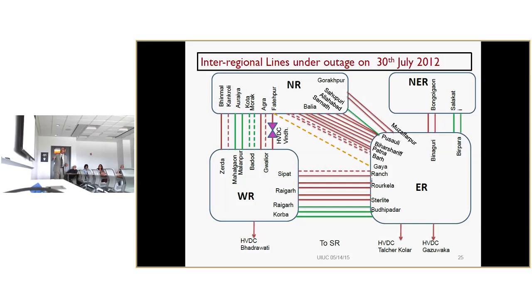And first the western region got disconnected from the northern region. All the power requirement, and they did not reduce their load, despite verbal communication, there is no automatic control. So despite verbal communication, they did not reduce their load. It started flowing from the eastern region. So it is like a two-area system. A lot of oscillations you will see. And one by one, the lines tripped because sometimes the current became very high and the voltage became very low. So we have seen tripping under zone 2 and zone 1 also in some places. So they tripped one by one, and finally the northern grid got disconnected from the rest of the grid.